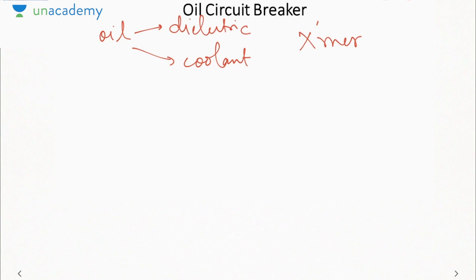Now, what happens in a transformer? Suppose there is a fault, an arc will be formed between the circuit breaker plates, due to which there will be a tremendous amount of heat produced which will vaporize the oil. And that vaporization or resolution of oil into component gases is used to detect the fault in the transformer, and that is the basic principle of your Buchholz relay. Okay, that is why oil circuit breakers are very important when it comes to transformers.